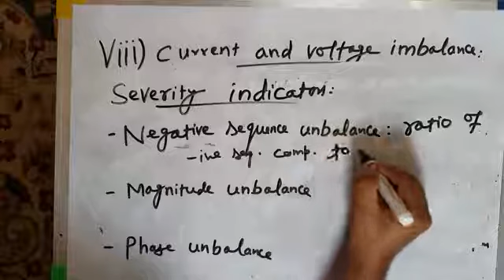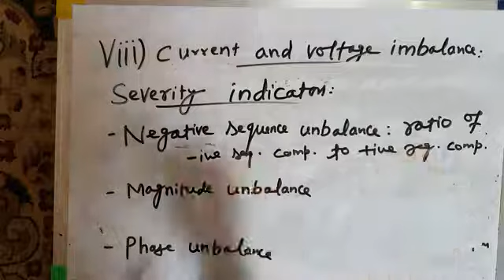Negative sequence unbalance is defined as the ratio of the negative sequence component of current or voltage to the positive sequence component. If your three-phase system is balanced, there are only positive sequence components. There is no negative sequence component. But as soon as your three-phase system becomes unbalanced, in addition to the positive sequence component, there is a negative sequence component also. The negative sequence component is indicative of unbalance in the system. The higher this ratio of negative sequence to positive sequence component, the higher is the negative sequence unbalance. So this is a severity indicator.